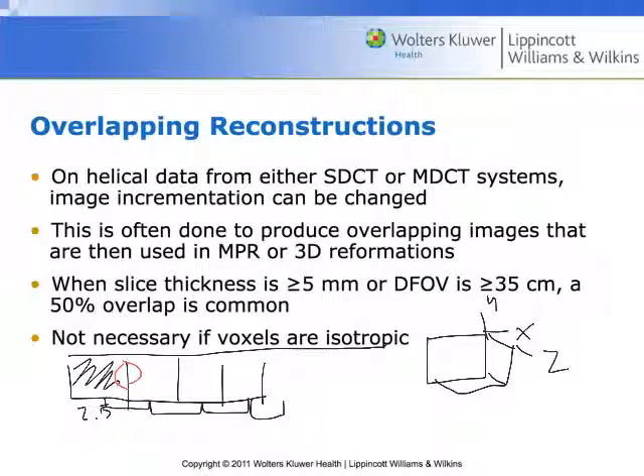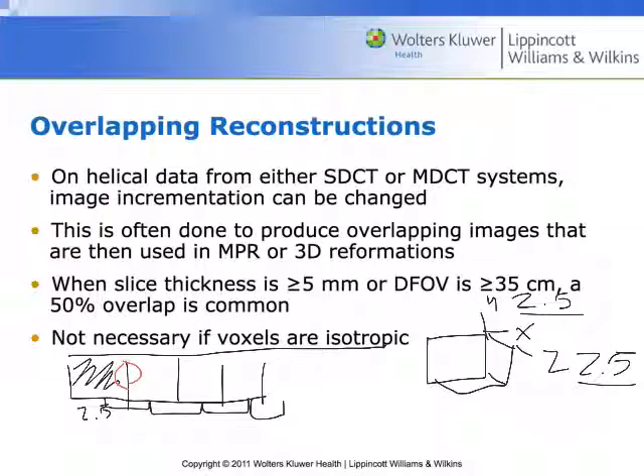In general, overlapping reconstructions are not necessary if the voxels are isotropic — if the slice thickness is 2.5 mm and we also only moved 2.5 mm (a pitch of 1), then we don't need an overlapping reconstruction. But if we're increasing the pitch beyond 1, we may need to produce overlapping reconstructions. Another case where overlapping is not necessary is if the slice thickness is very thin — 0.5 mm or less with a field of view less than 25 cm — overlapping reconstructions generally are not worth the inconvenience of storing the larger dataset, as there's not going to be anything really added to the information.